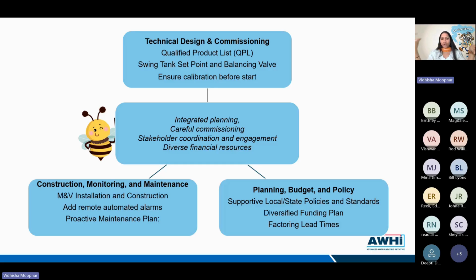Other than that, there were some data discrepancies when we started with the commissioning and monitoring and verification part. The reason being, some of the flow meters were not properly calibrated. That was another lesson learned - make sure all your sensors and flow meters are properly calibrated before you run the system, so you don't get different or negative data coming up during monitoring and verification.